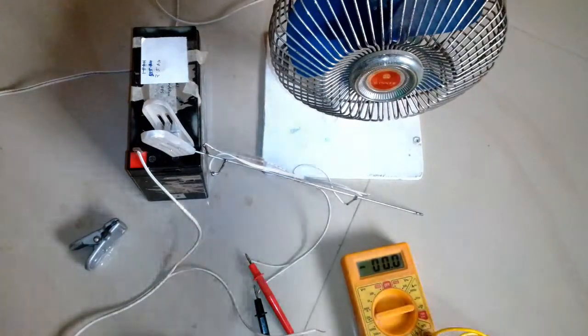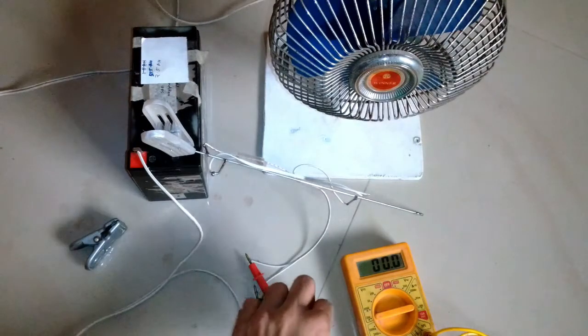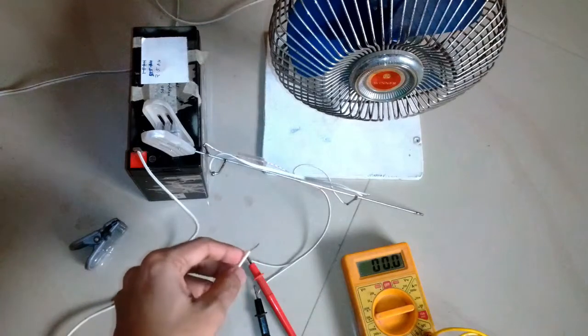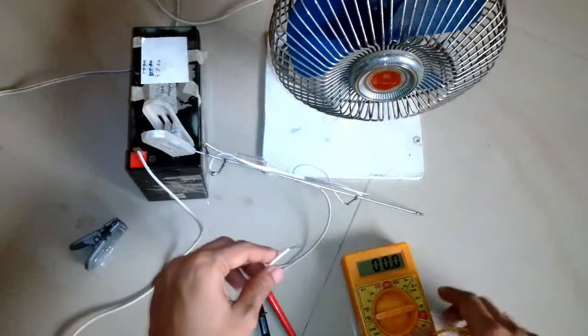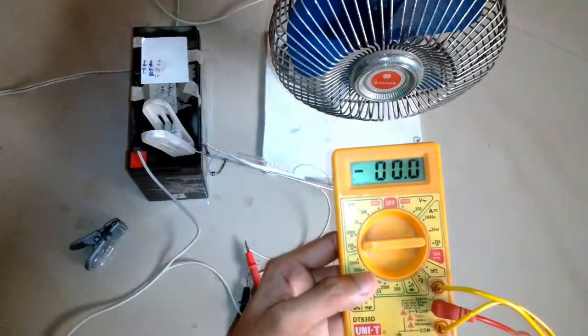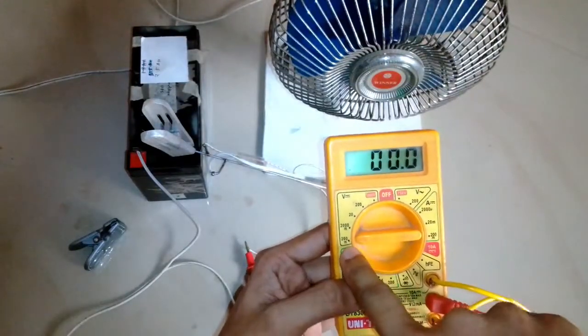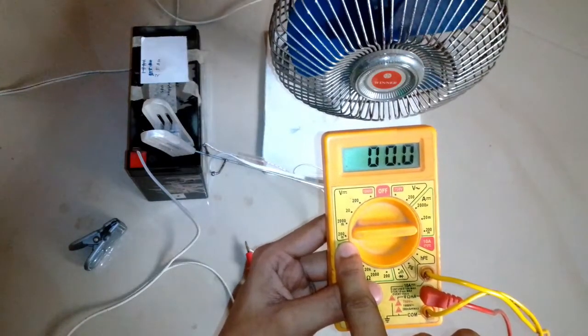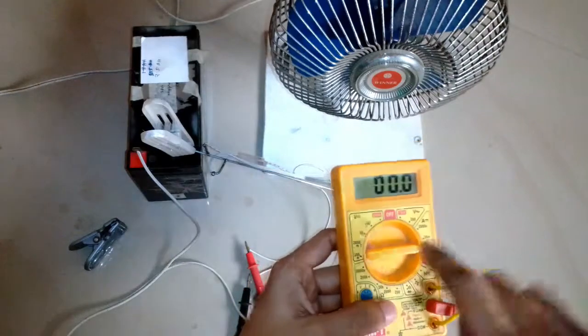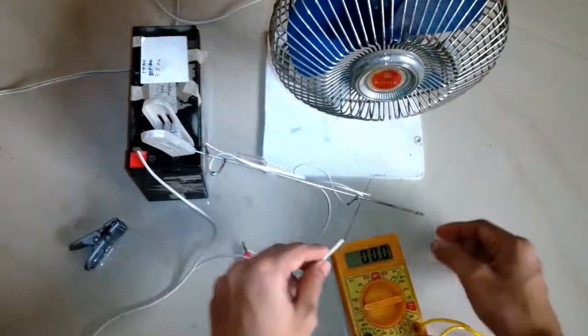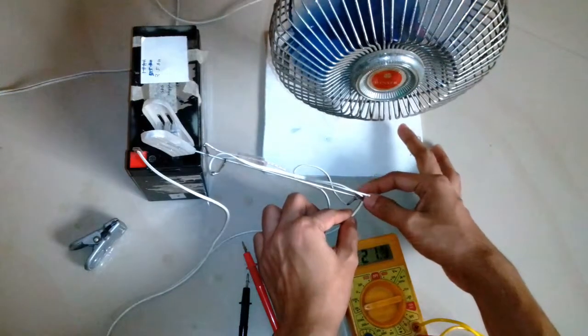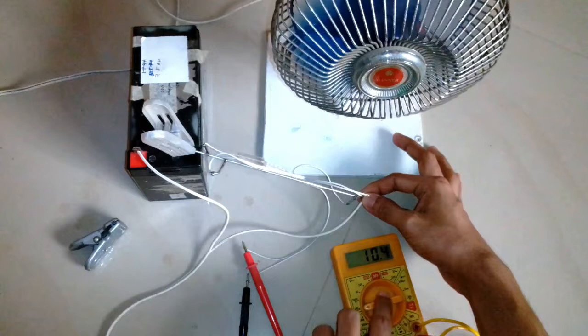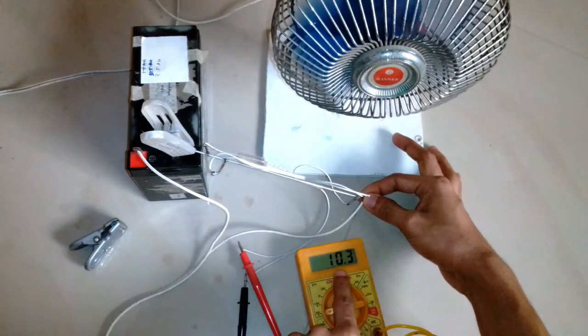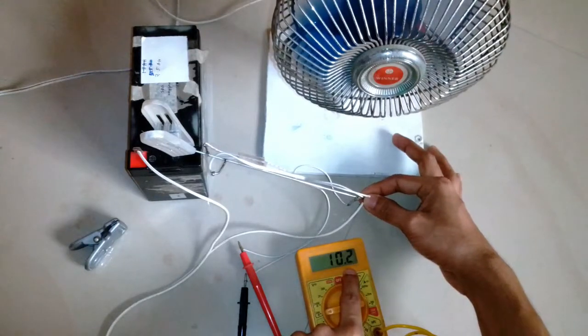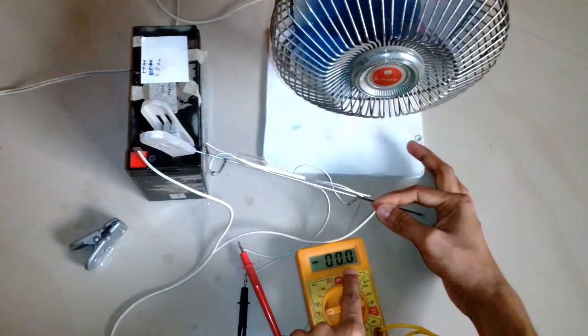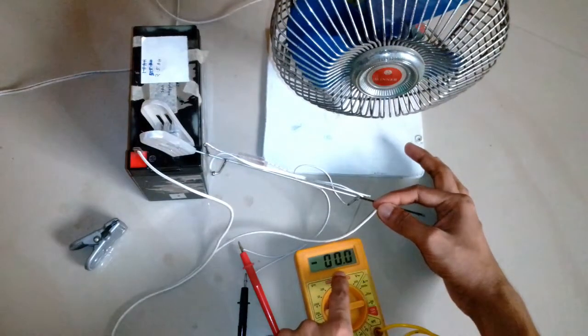So right now I have connected my multimeter with the longest distance, the 10 millivolt drop section of the shunt at 1 amp, and you can see the multimeter is set to 200 millivolt setting. Now as I connect it with the wire, the current starts flowing through the shunt, and you can see the voltage drop is 10.3. So if I move the decimal point one digit to the left, it becomes 1.03 amps.